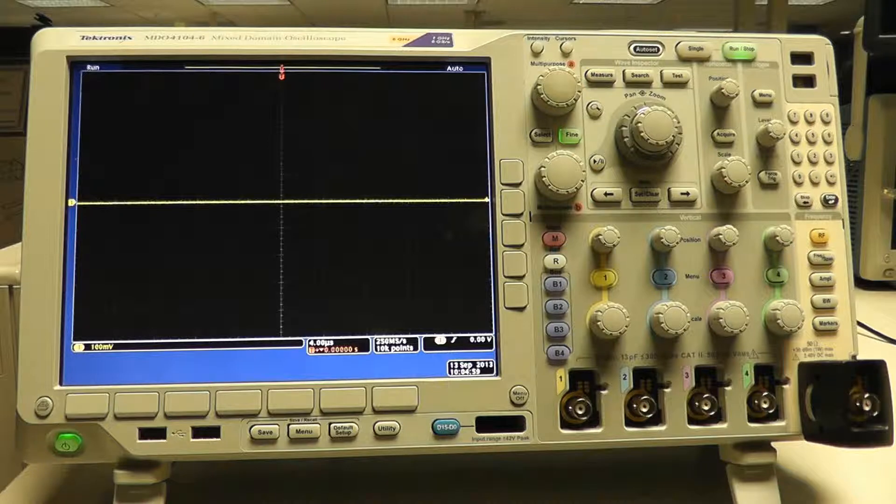For the 4000 series scopes, a live network connection must be made on the scope in order to set and save LAN settings. If the scope does not have a live network connection, the IP address will default to 0.0.0.0.